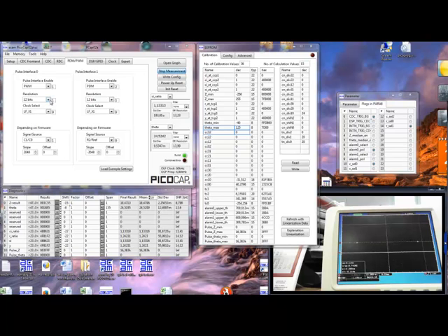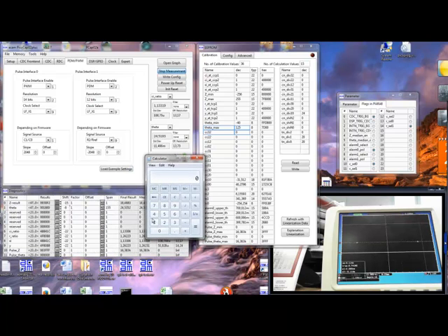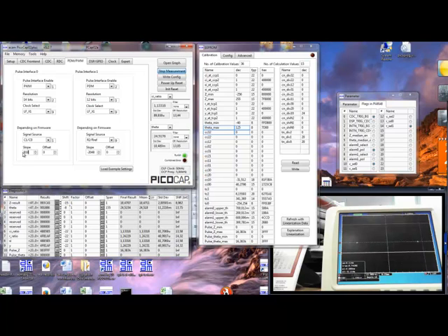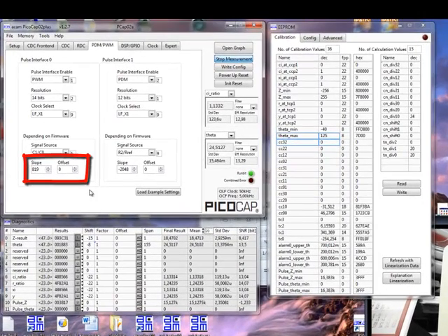After that basic settings, I can now configure the PWM output to my requirements. I select, for example, 14 bits for the output and will now calculate the slope and offset parameters I want to fill in here. So 14 bits corresponds to 16,384 steps, and I divide that by 20 PSI, which is the range I formally configured, between 5 and 25 PSI, if you remember.